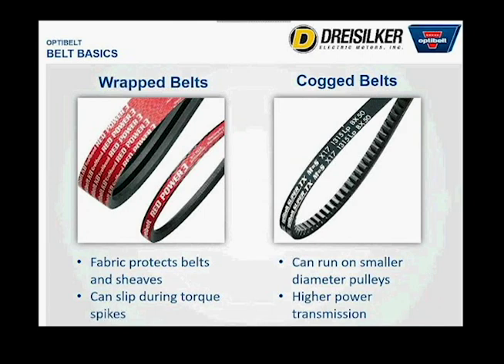First you have wrapped belts, and these were the original belts invented way back with Gates. They are the same rubber core with a tension cord, except the difference is they have fabric on the outside. Ours have 2 layers, some have 1, but most you'll find in the industry have 2. What this does is the fabric helps protect the belt from any sort of grit, oil, and wear that's in the sheaves. This is very helpful in sandy environments and ones where you have a lot of contact with anything that could damage the belt or the sheaves. It acts as a layer of protection and also helps dissipate heat.